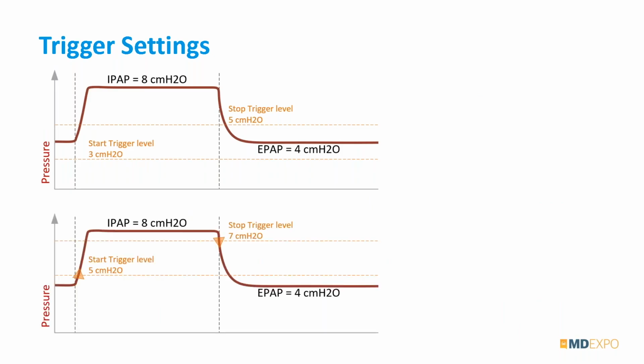So in such a situation, you would have to amend your trigger settings on the gas flow analyzer and adapt them to the new situation and say, okay, I'm going to have to move them up to 5 and to 7, and then only can your gas flow analyzer measure the parameters again. So as you can see, if you have to change the trigger settings, it can be quite challenging actually to figure out the correct settings.